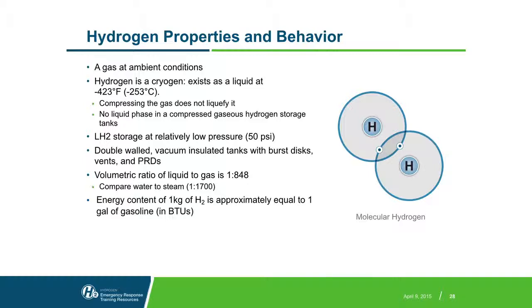So if you were to burn a kilogram of hydrogen, which we're not doing, and you burned a gallon of gasoline, you'd get about the same amount of energy out in BTUs, which is British thermal units. It's a standard way of measuring energy output, but the point being that it's about the same energy content. What we're doing in the fuel cell is an electrochemical reaction that's generating electricity. So there's no combustion. But when I say that this unit, again, holds about 75 kilograms of fuel, you can think about that as about 75 gallons of gas.